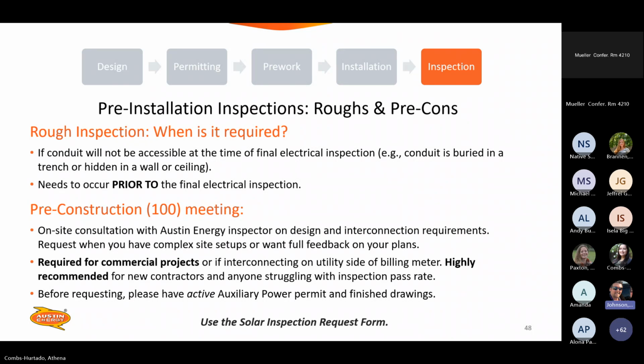Pre-con, on-site consultation with Austin Energy Inspector on design and interconnection requirements. So with auxiliary permits, and Megan, I think auxiliary permits have the pre-con for residential, but commercial, because they get a building permit generated automatically, the pre-con goes on the commercial. I'll just say for A, B, and C, that's correct. But if you need a pre-con for a solar aux permit, just use the solar inspection request form, and you won't have any issues getting it scheduled. And it is required for commercial. I just wanted to clarify that. I don't think I made that clear enough earlier. Required every single time for every single commercial project and for any residential project that you just want feedback on.